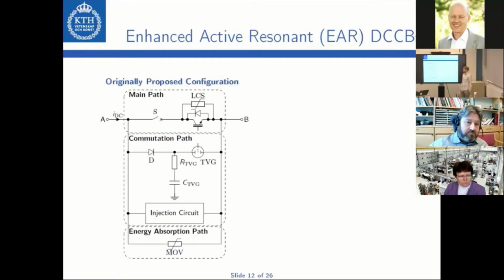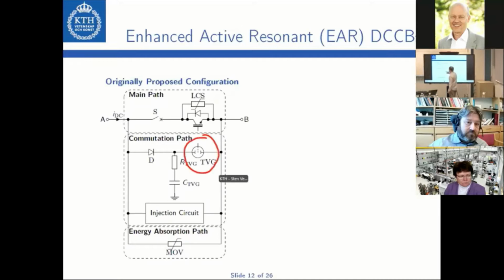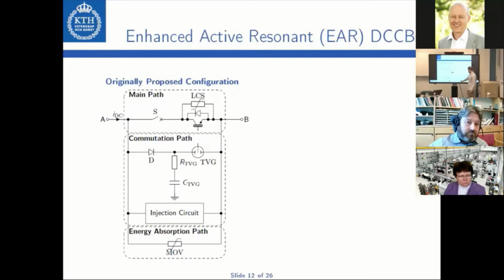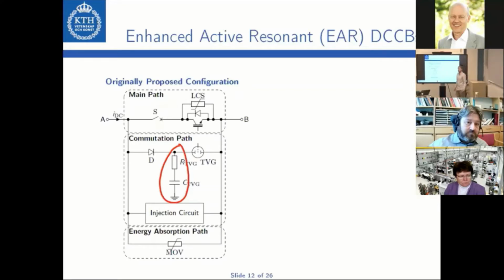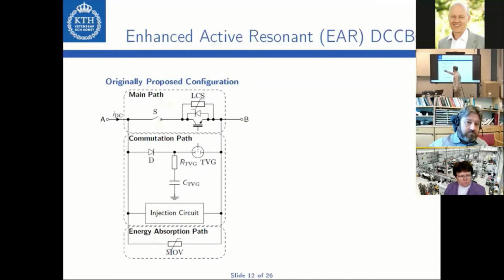Let's now have a look at the enhanced active resonant DC circuit breakers. On the left-hand side, you can see the originally proposed configuration. As you can see, the main path is similar to the hybrid DCCB. Here you can see the triggered vacuum gap in the commutation path. An RC circuit is connected to the anode of the triggered vacuum gap to provide a high voltage potential that is needed for the triggered vacuum gap to operate, to satisfy the minimum voltage requirement. The RC circuit is pre-charged from the DC line through this diode. The injection circuit in the commutation path is needed to extinguish the discharge in the triggered vacuum gap with an artificial zero crossing. This is similar to a current injection DCCB.